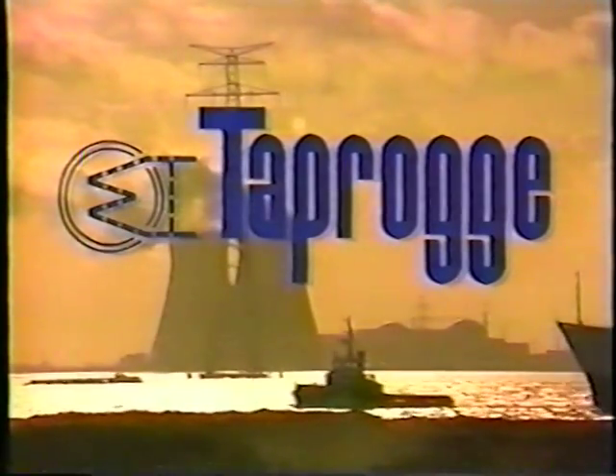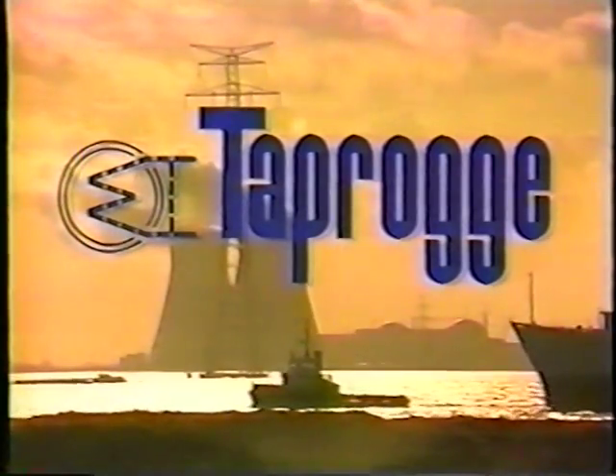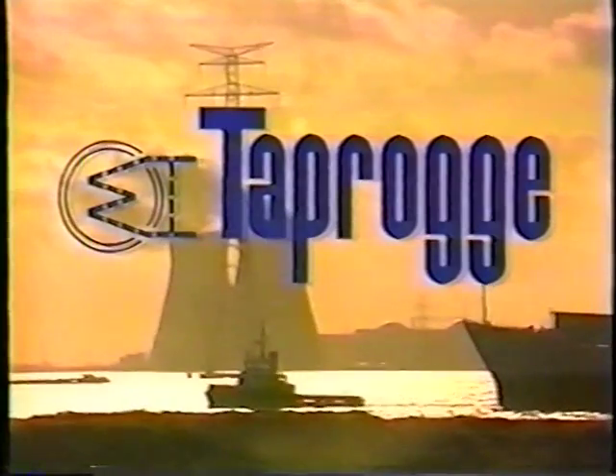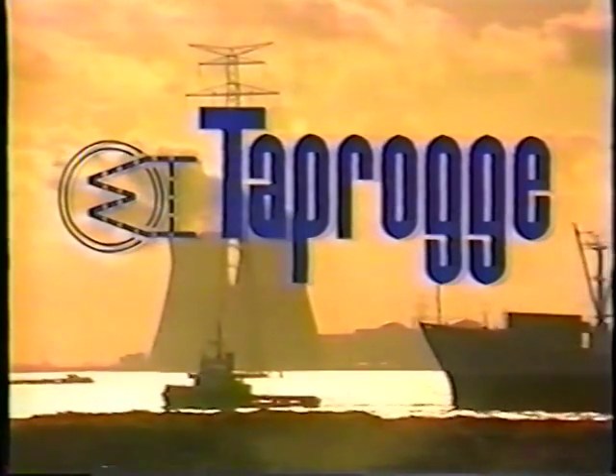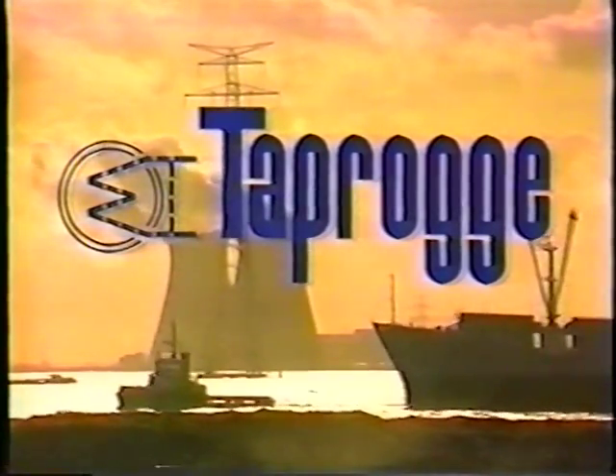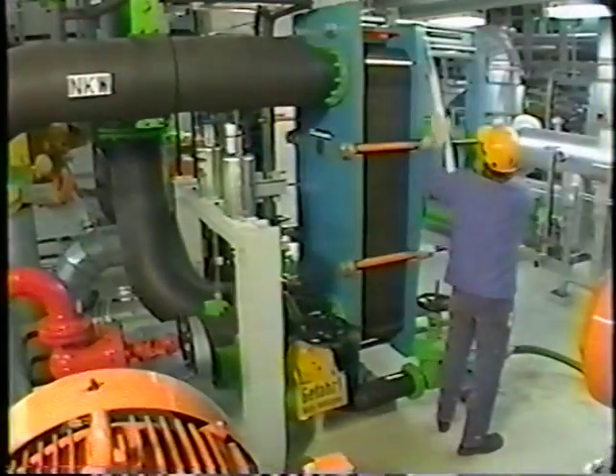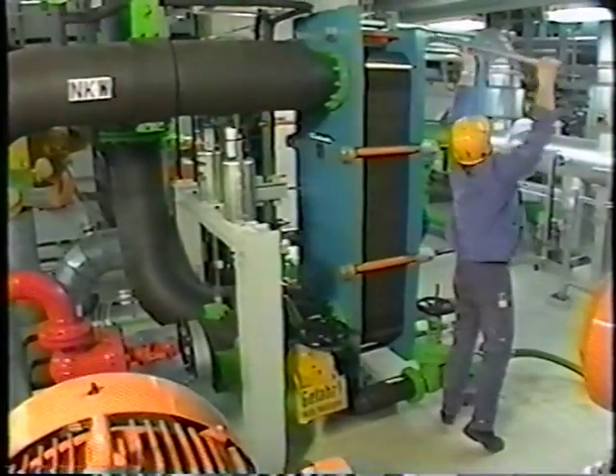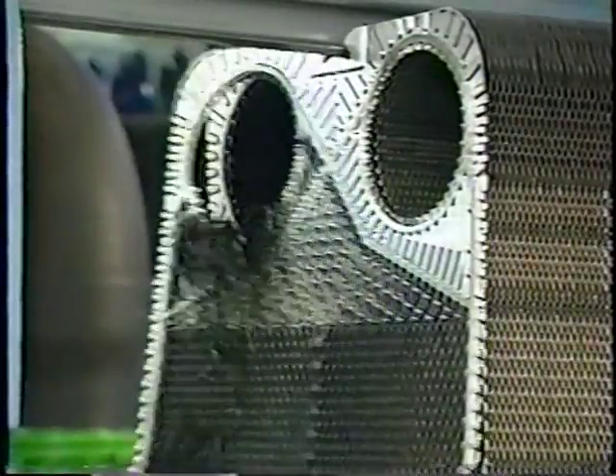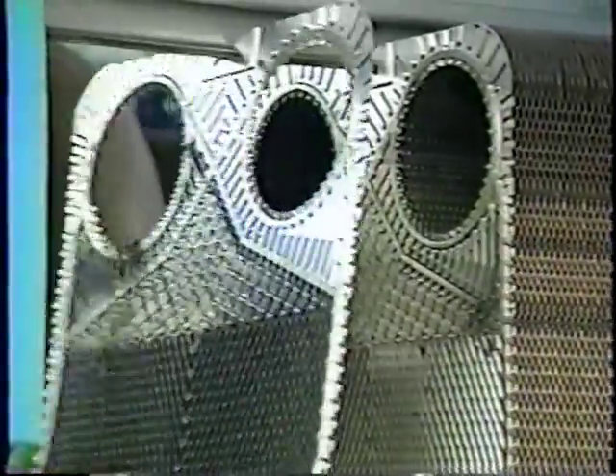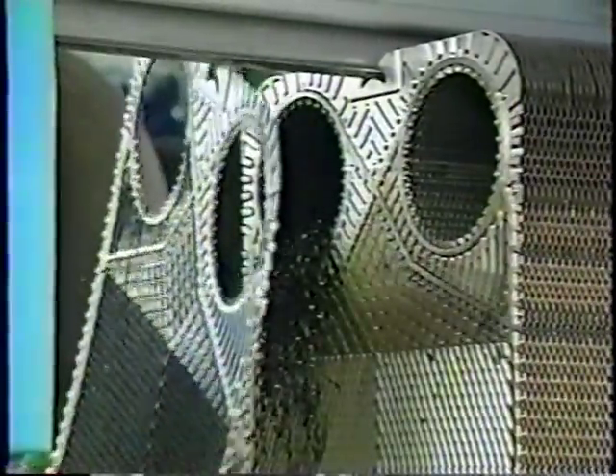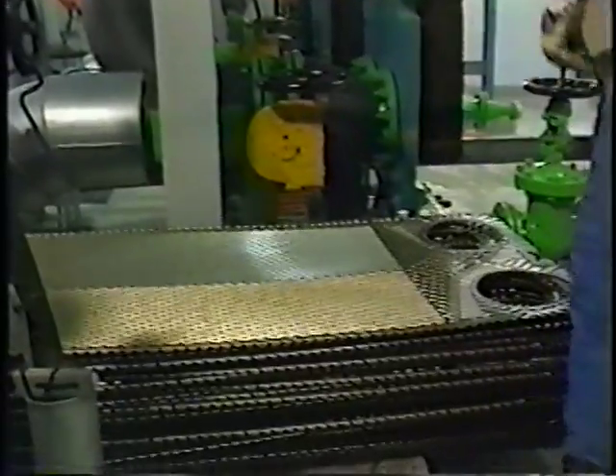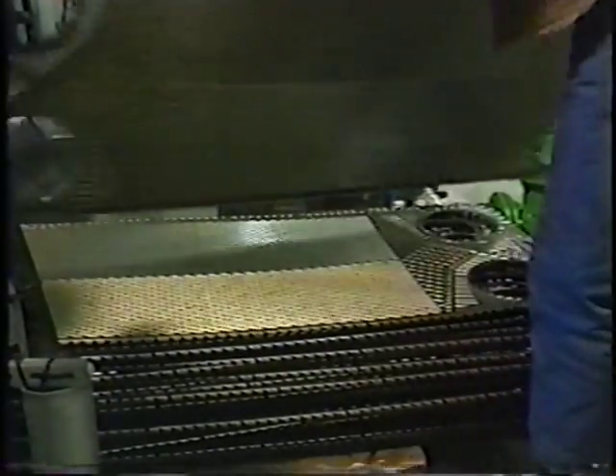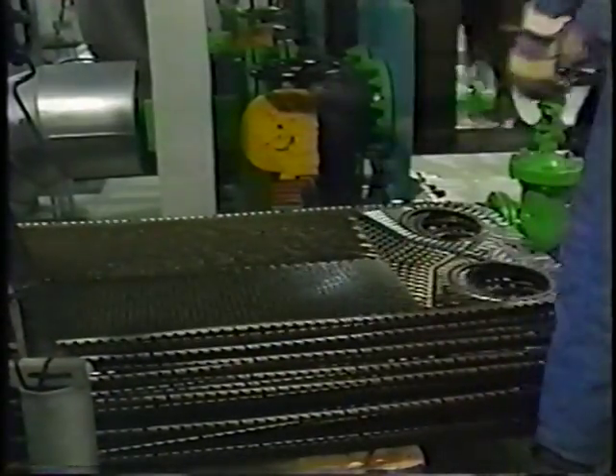Wherever large quantities of cooling and process water are used in power stations and industrial plants, fouling problems occur. In this power station, the plate heat exchangers have to be cleaned regularly due to large quantities of fibrous material and mussels being carried in the cooling water. Consequently, the entrained debris has to be repeatedly removed in this labor-intensive and expensive manner, often during emergency shutdown.